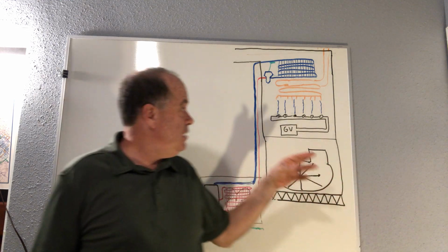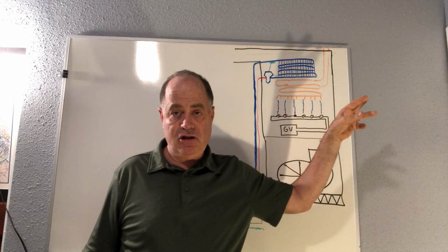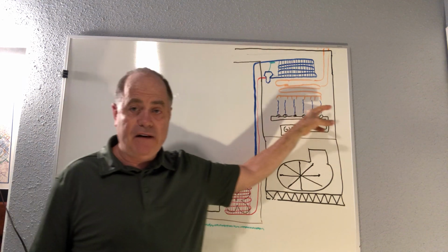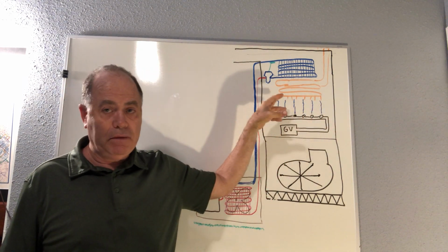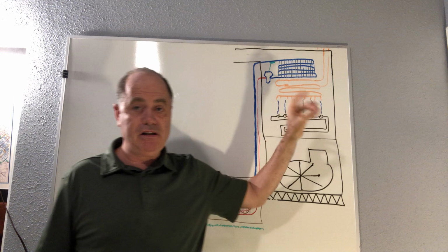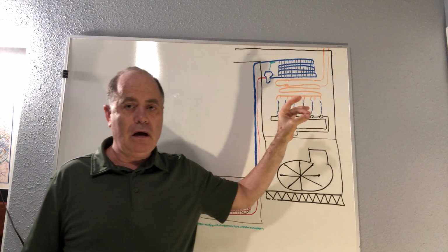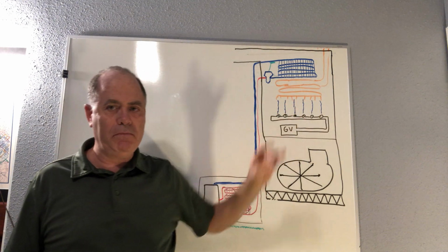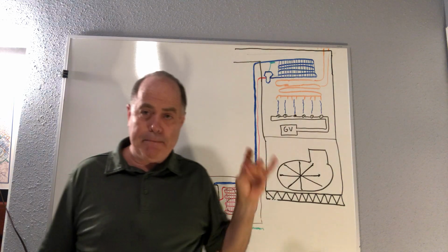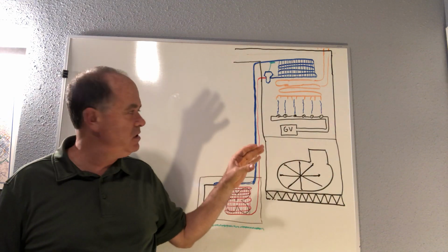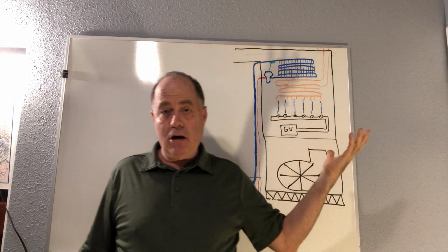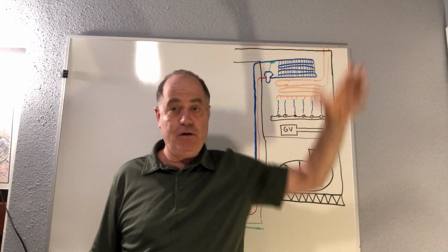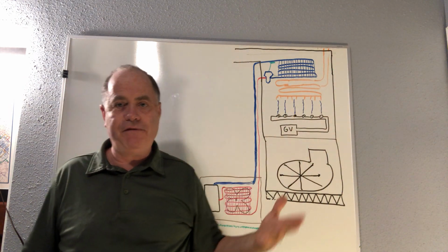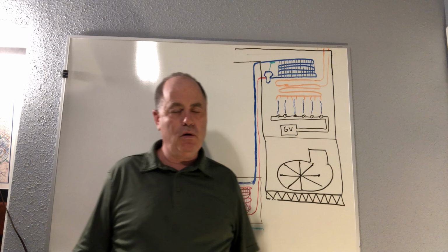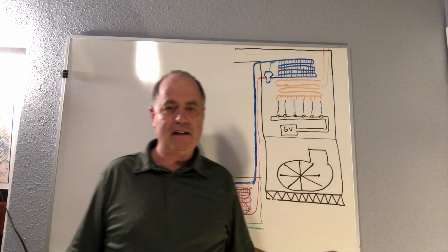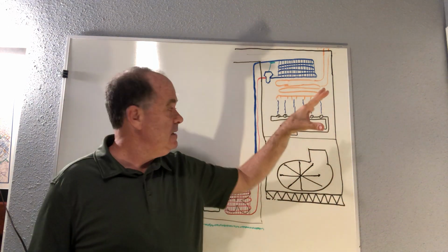First of all, you'd have to have a terribly cracked heat exchanger. Second of all, you'd have to have orange in your flame and be producing a lot of carbon monoxide, because a perfect flame, a complete combustion, has no carbon monoxide in it. Not that we get perfect combustion, but we get very close. If you want to take a carbon monoxide meter and put it up to your supply air vent, I defy you to read more than 4 or 5 parts per million, even if you had a slightly cracked heat exchanger.